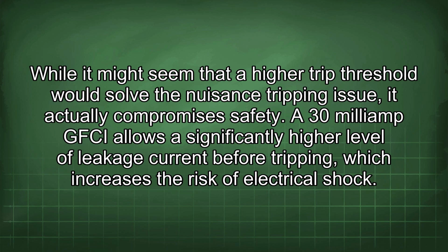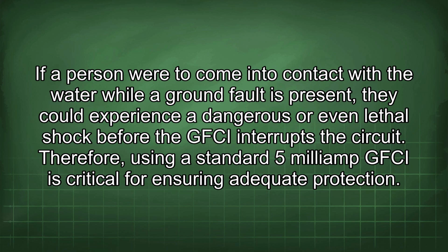A 30 mA GFCI allows a significantly higher level of leakage current before tripping, which increases the risk of electrical shock. If a person were to come into contact with the water while a ground fault is present, they could experience a dangerous or even lethal shock before the GFCI interrupts the circuit. Therefore, using a standard 5 mA GFCI is critical for ensuring adequate protection.